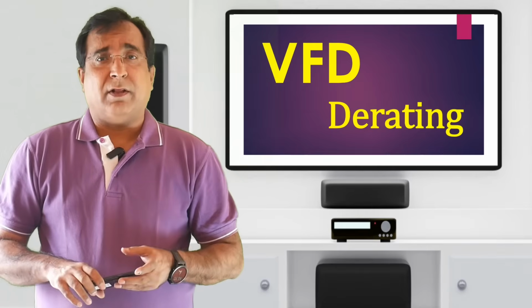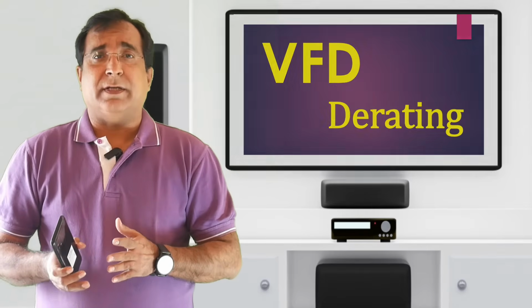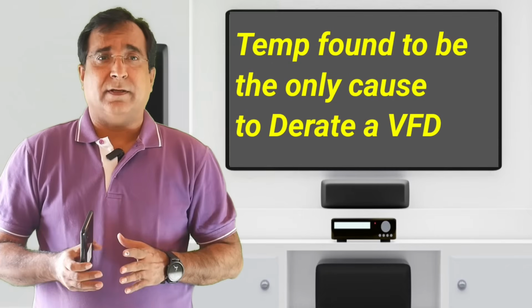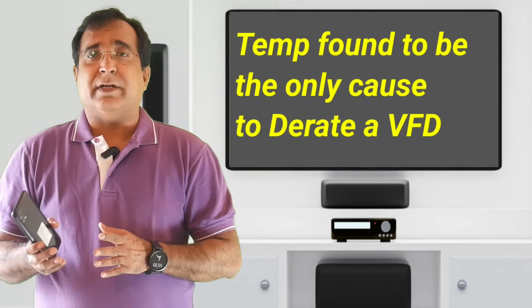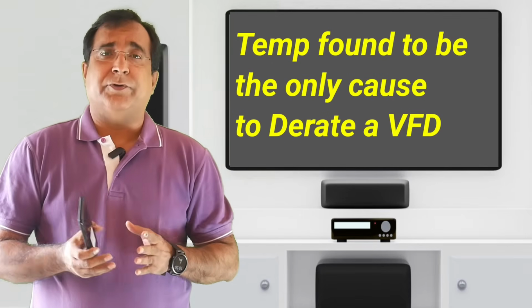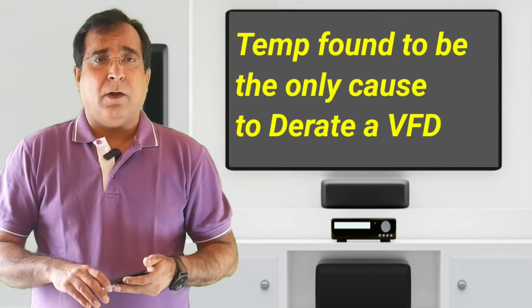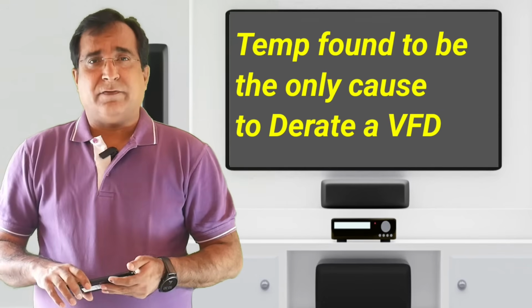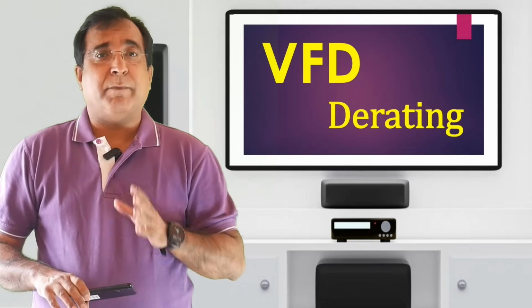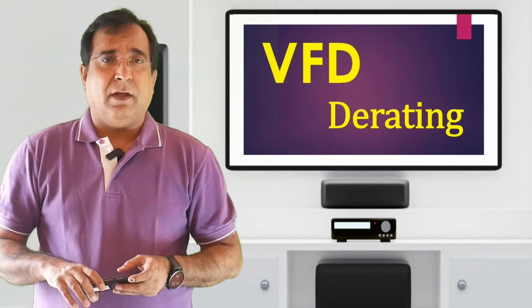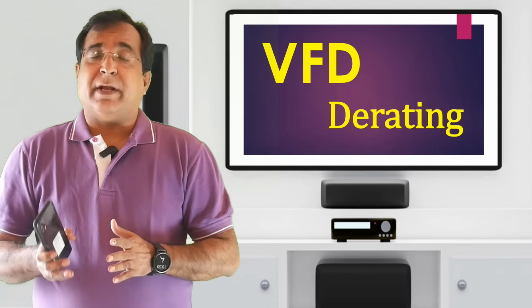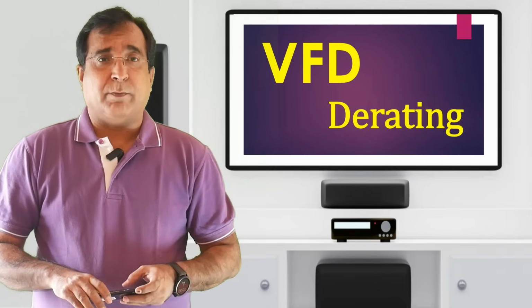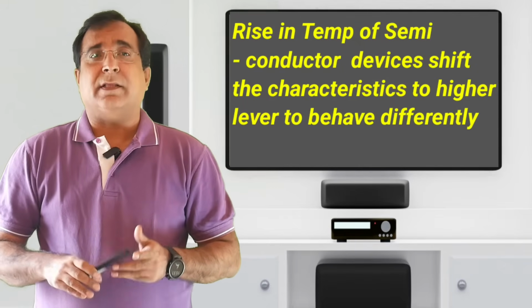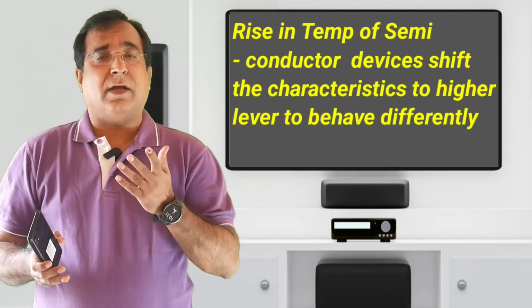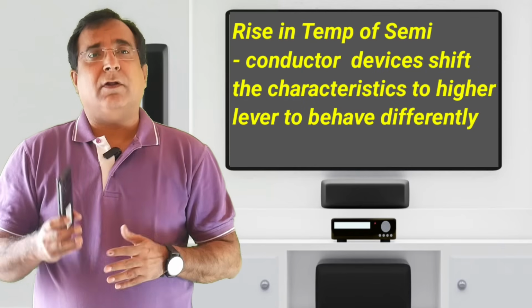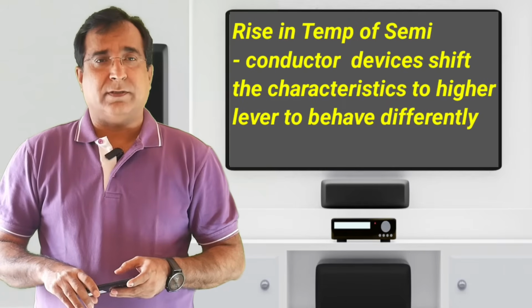You must have observed that in all the factors we have discussed so far, the temperature of the VFD was rising, be it higher altitude, ambient temperature, IGBT switching frequency, or a continuous duty cycle. So why does this rise in temperature cause the VFD to derate? What happens inside a VFD? We have studied that with any rise in semiconductor temperature, the characteristics of electronic components like IGBTs, capacitors and other circuit components change or shift to another level, or may cause breakdown of the electronic components.